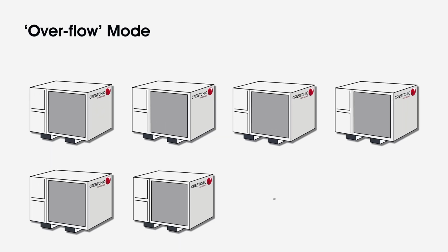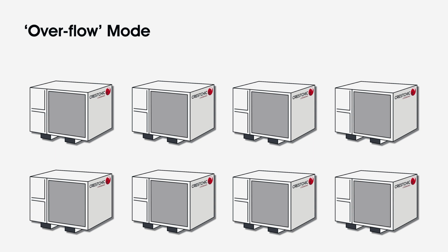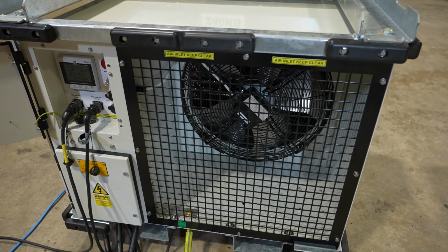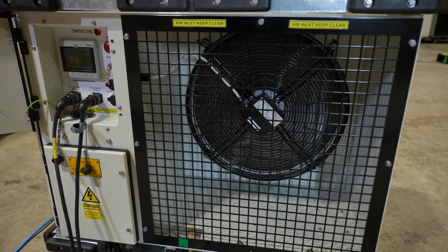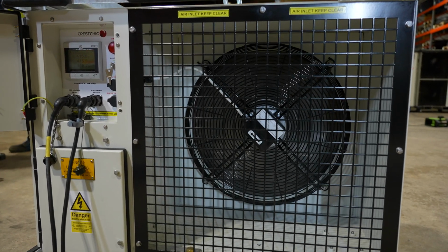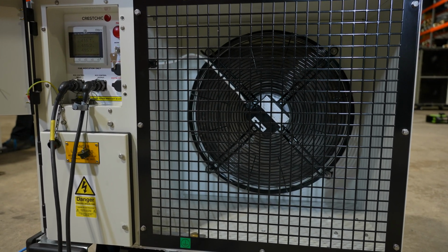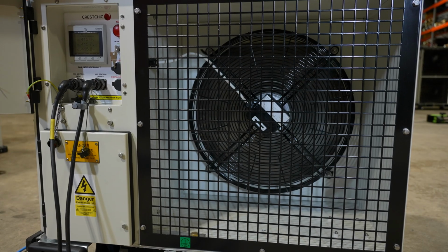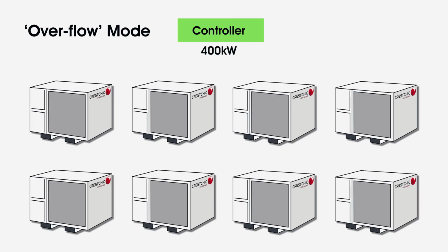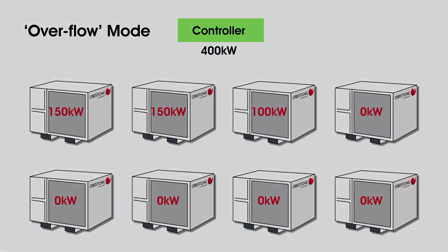The second method is overflow. In this mode, the load is put onto the first load bank from the controller, and once this exceeds the first load bank's capacity, the additional load goes onto the second load bank, and so on. An example of this is if 400 kilowatts was applied, with each load bank having a nominal load capacity of 150 kilowatts, the first and second load banks will have 150 kilowatts applied, with the third load bank having 100 kilowatts applied. This control method is more common for rudimentary genset testing.